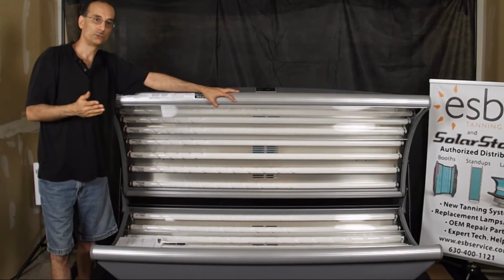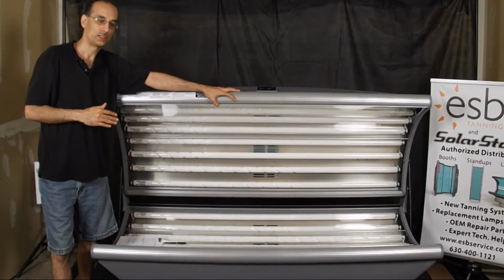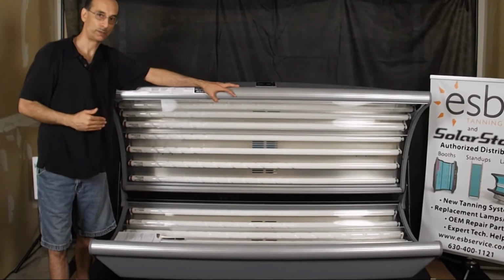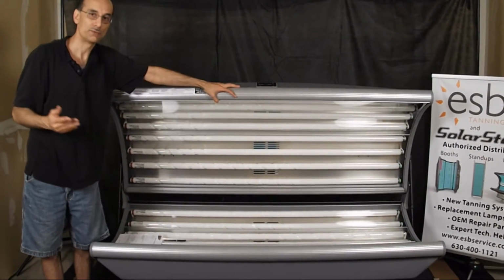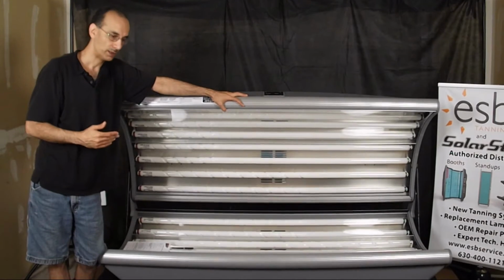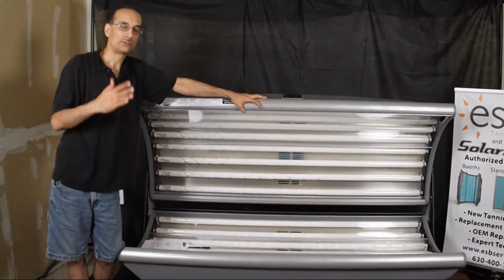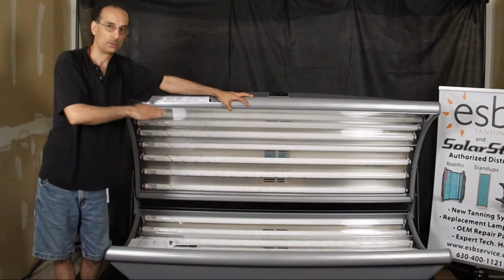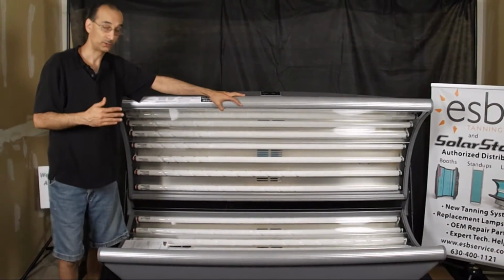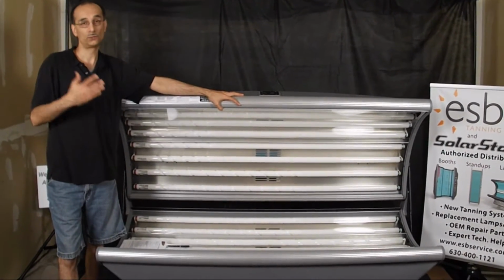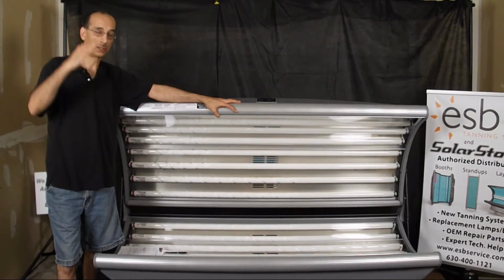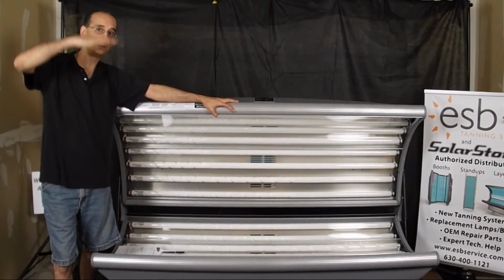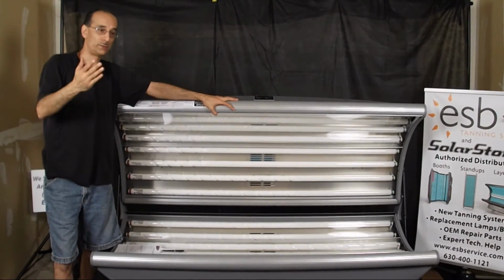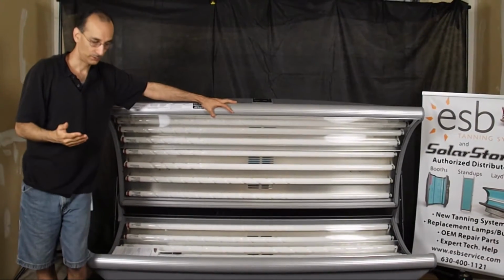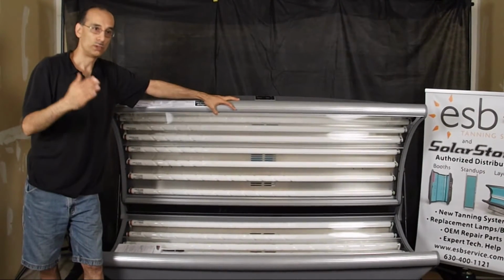You would only need a buck booster if you're so far out of that range and you need to put it into that range. For instance, if you had 135 volts at your receptacle. A buck booster has two functions, one or the other, depending on how it's wired. Either it's going to be a bucking transformer or it's going to be a boosting transformer. Bucking means it's going to drop it, boosting means it's going to increase it. So in my example of 135 volts, you would need a bucking transformer, which would typically drop the voltage 17 volts.